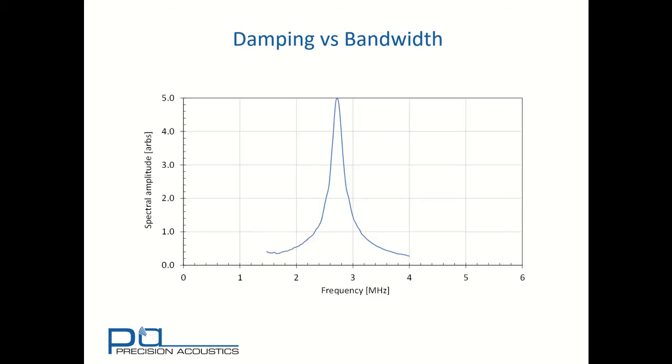That concept is very useful when we come to consider transducers. We'll start here by looking at a relatively narrowband transducer. Here we can see that the output amplitude, whilst centered at about 2.7 MHz, falls off rapidly as we move to either side of that center frequency.